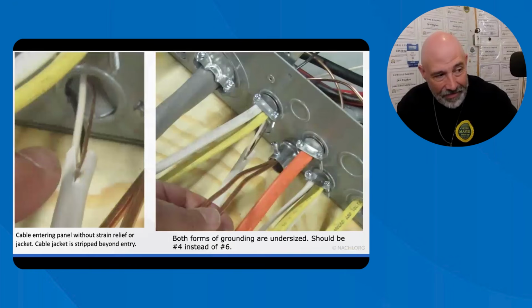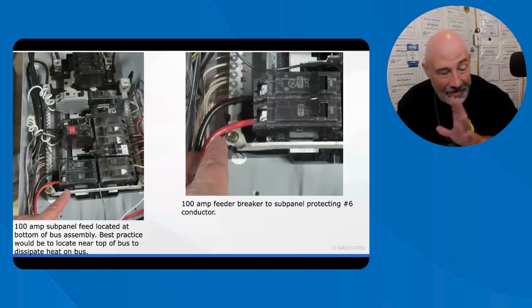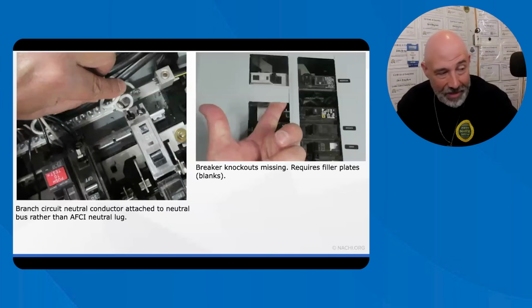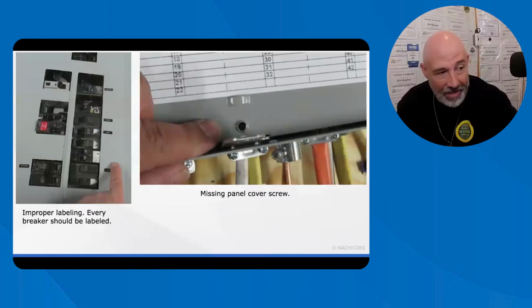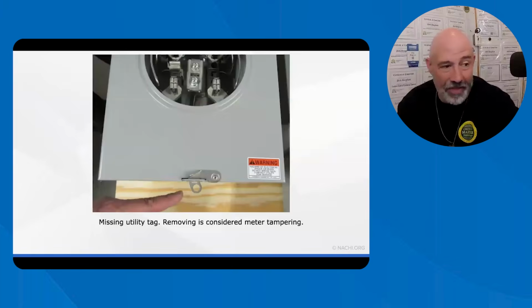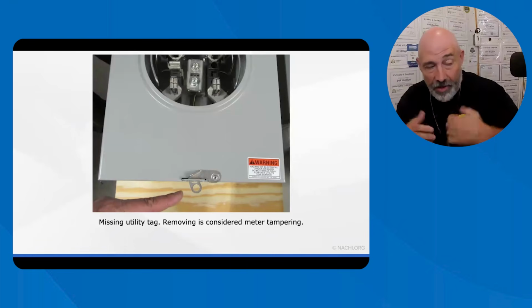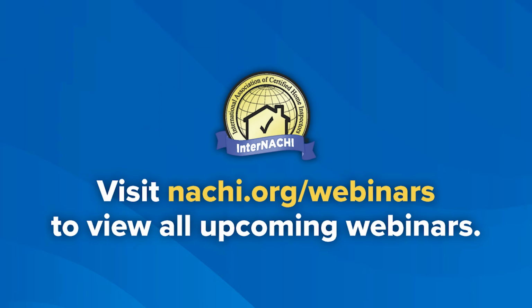Same thing here. You've seen this before. Can't tell you how many times. Anything that looks outside the normal. Matter of fact, I see it too often and it just makes me cringe. I've gone to so many houses where they're missing screws, they're not labeled properly, there are knockouts missing. Anything that's tampered with, make sure you're keeping an eye on it. Missing the utility tag is also considered tampering. So if you see that on a meter box, and if that meter box has openings, make sure you're calling that out too. But other than that, AJ, this is it.